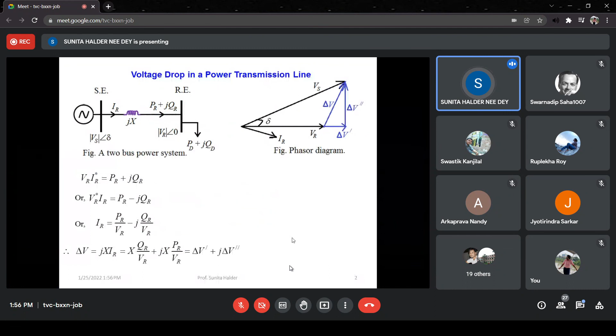What do we need for the further classes? The concept is that when we want to control the voltage drop in a transmission line, we need shunt compensation. This is the first concept. Now, shunt compensation will be capacitive when voltage is very low and power is very high. In the heavy loading condition, under-voltage problem, we use capacitive compensation. In a very easy way, the load is very high, and load means inductive load, so the inductive current we have to compensate by capacitance. On the contrary, when the load is low, that means the inductive current is low, then to bring it to the normal condition, we have to connect some more inductor. So the compensation will be inductive. This much gist is required for the further classes.